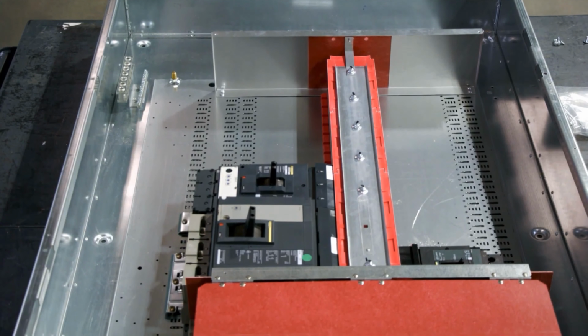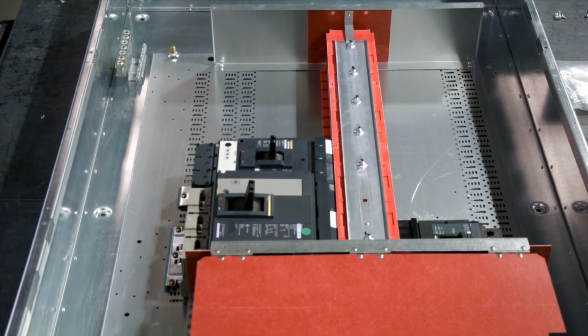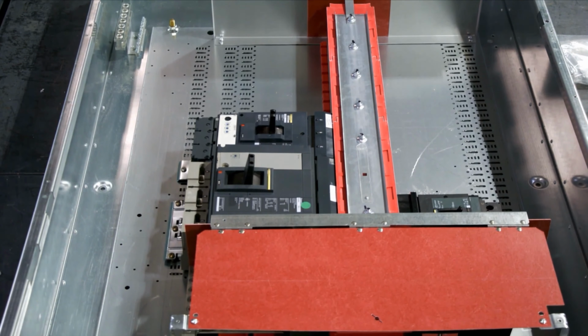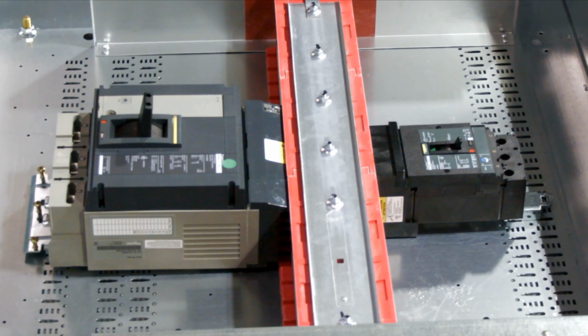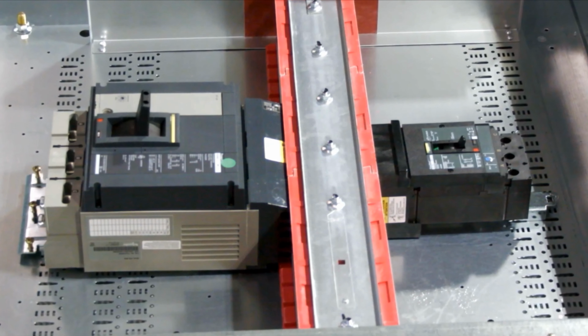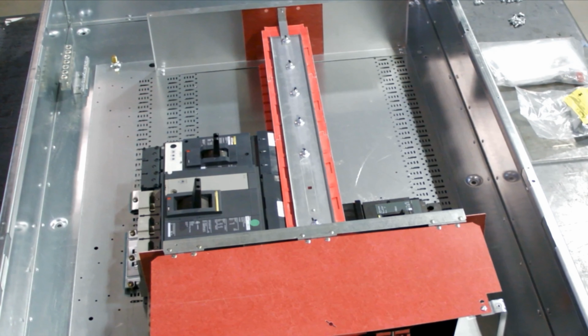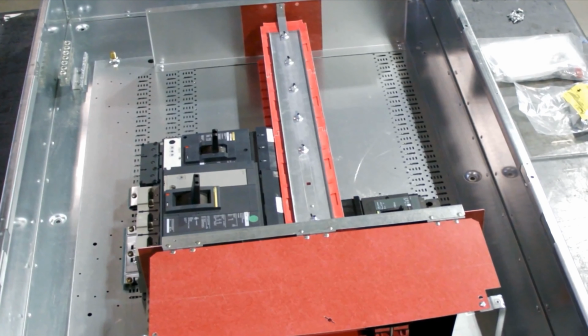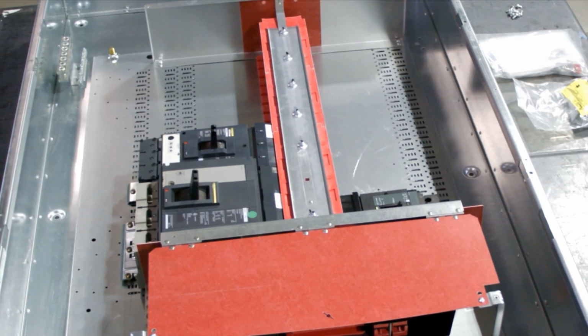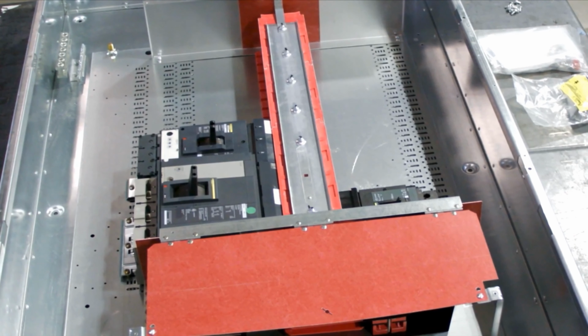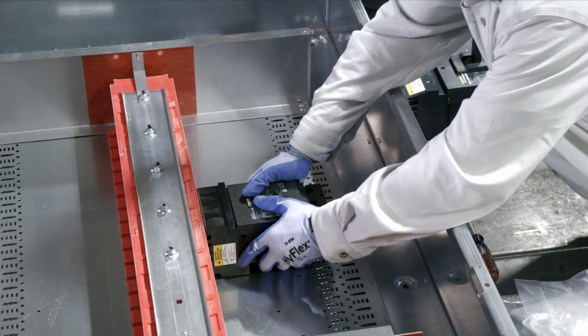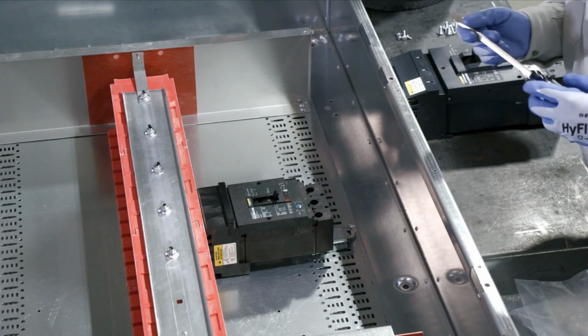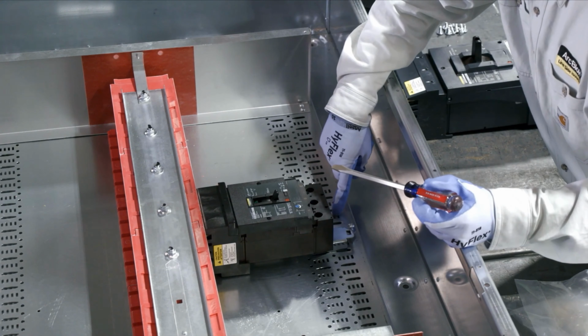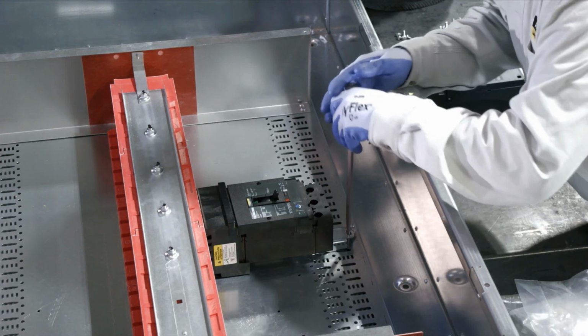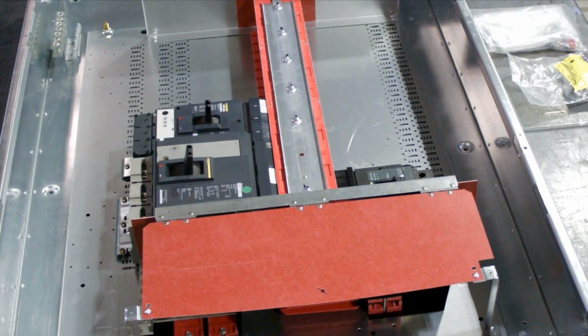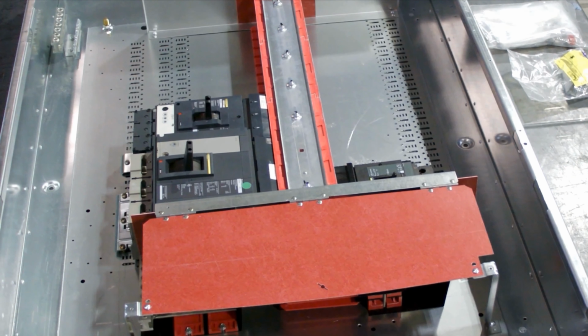What's unique about this I-line circuit breaker system is its ability to allow dissimilar circuit breakers to be mounted across from one another. For the first time, you can actually mount a 1200 amp circuit breaker across from a 15 amp. This innovative game changer gives you unprecedented flexibility in a panel board. It allows you to make last-minute changes and adaptations to any project, since circuit breakers can be installed quickly and easily. And unlike other panel boards that cut off the space in the panel, I-line lets you add breakers as needed down the road. Simply buy I-line in mounting inches, and there will always be inches left over.